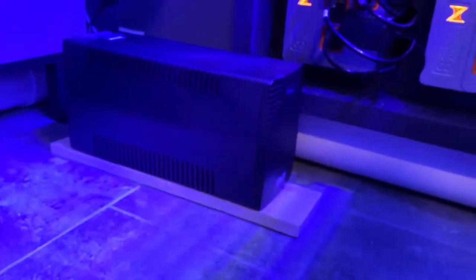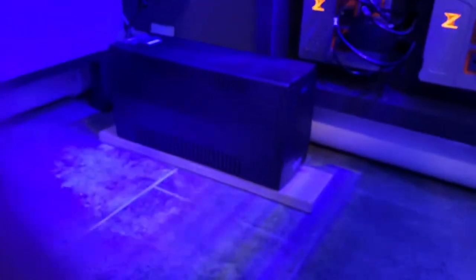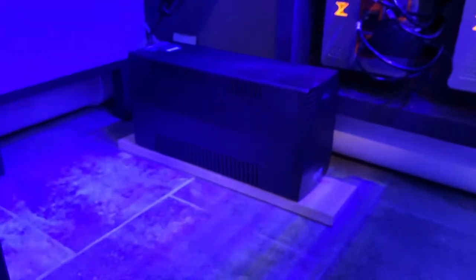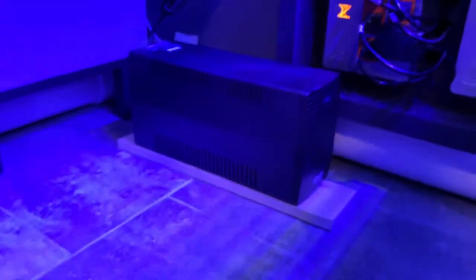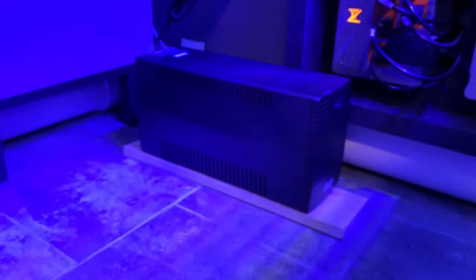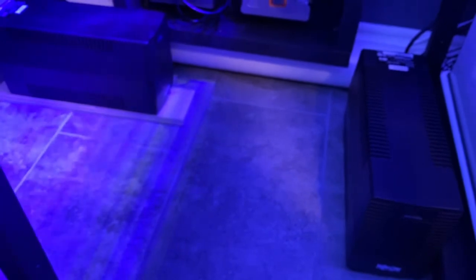One more recent addition is a couple of 1200 watt UPSs. When the LED lights are full blast and the 600 watt heaters are on, there's about 1,000 watts being pulled off of each 15 amp circuit. So I have the heater split up and the rest of the electronics split up pretty well, so that power is evenly distributed across those two 15 amp circuits.